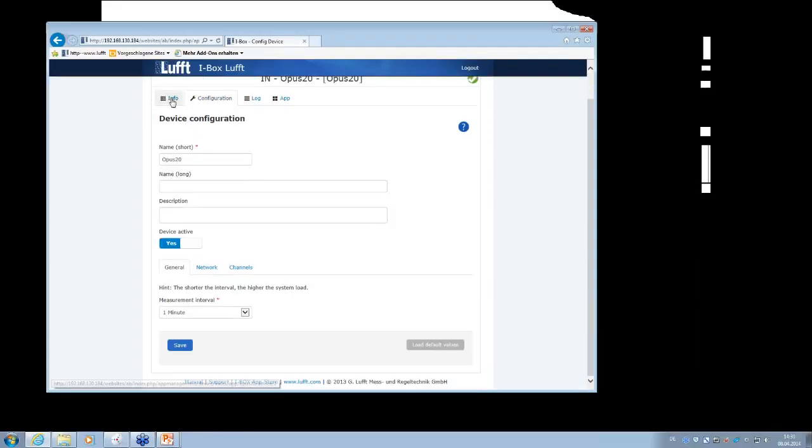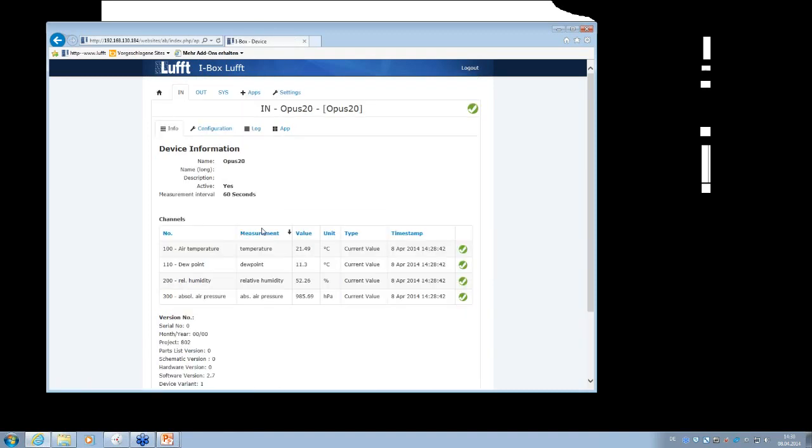So again, we try to go back, see if it's now ready or not. No, now we are ready. Okay, so now you see, from channel 100, which is air temperature, you will get the temperature, which has a value of 21.49 degrees Celsius, which is a current value, and you will get a timestamp. And you see the sign here that everything is okay with this value. You get the dew point, the relative humidity, and the air pressure. So that's it. Now you will always get new values every minute.